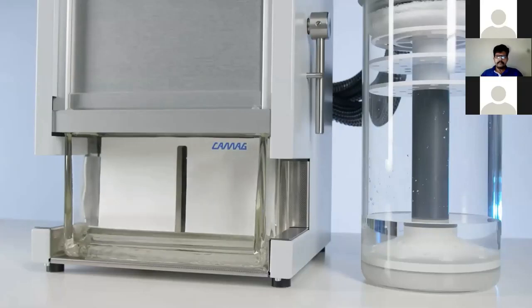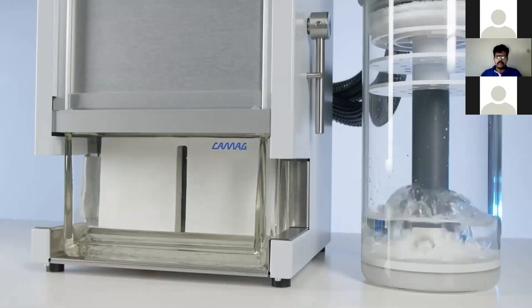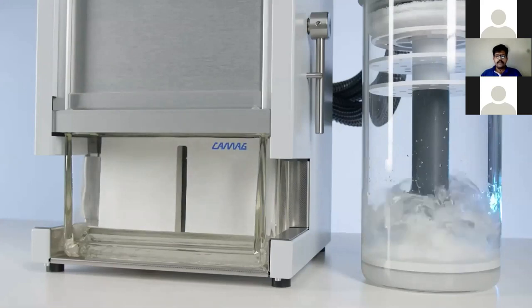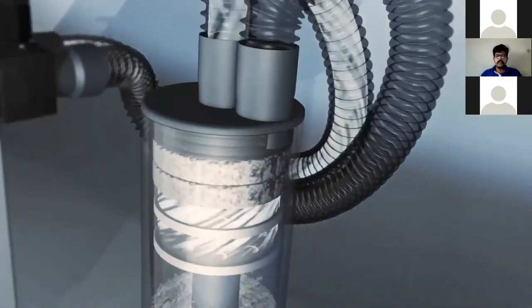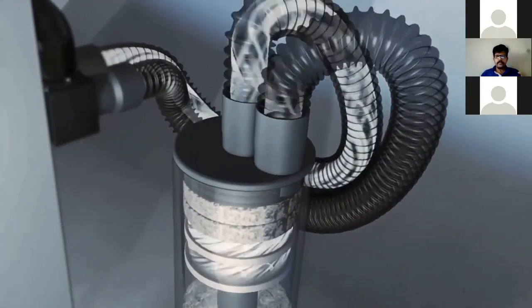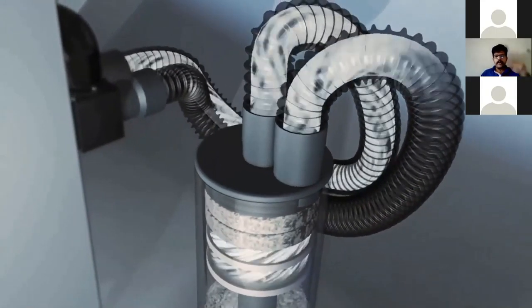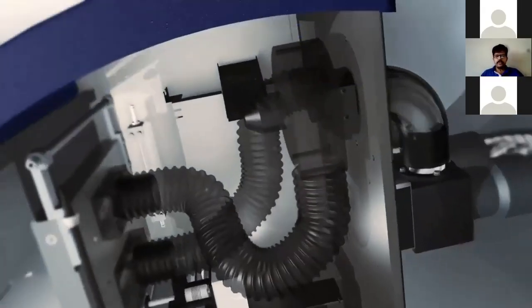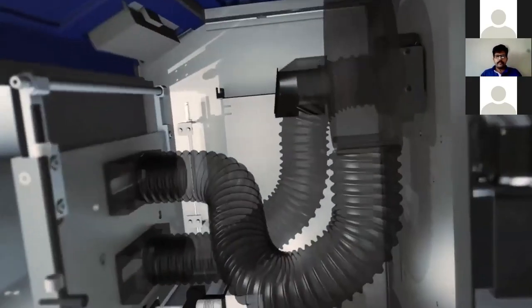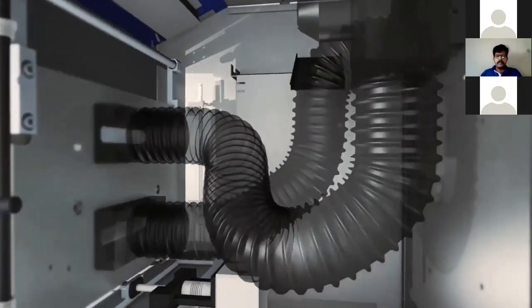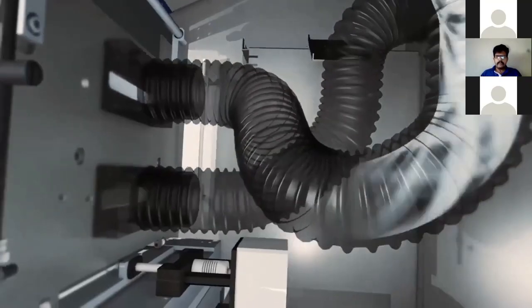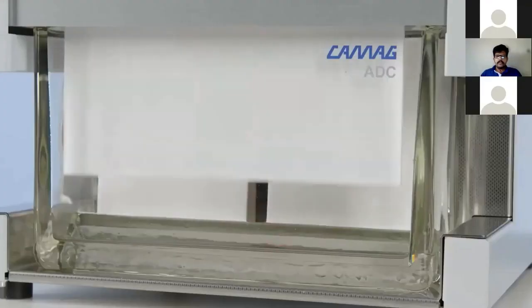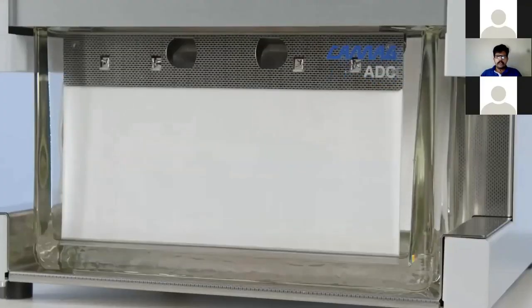The automatic developing chamber ADC2 has the optional humidity control on the right-hand side, which is responsible for obtaining reproducible results from plate to plate. You can see the mechanism, how the air flows and saturates the chamber and removes the excess moisture. Perform chromatography under different climatic conditions and compare chromatograms created in different labs and results obtained from different batches. Chromatography is started by lowering the plate into the developing solvent.